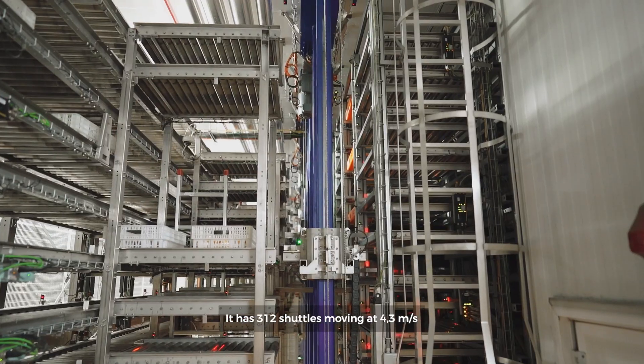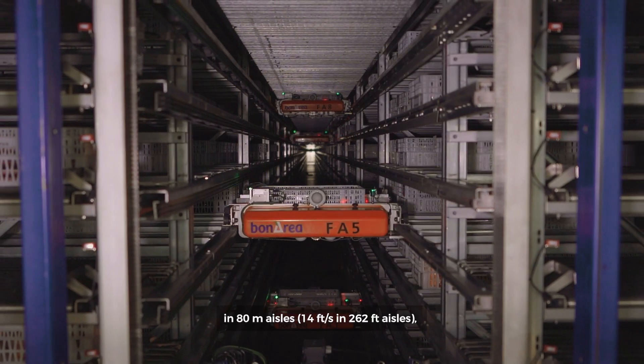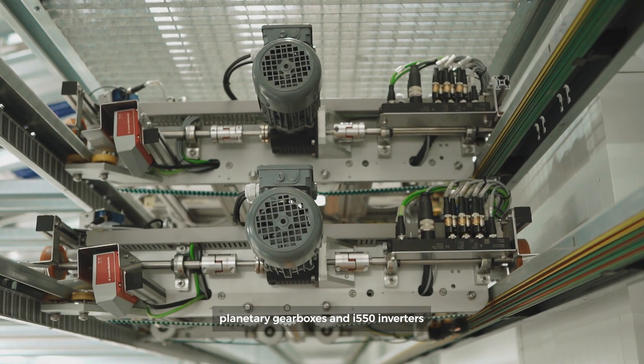It has 312 shuttles moving at 4.3 m per second in 80-meter aisles, driven by Lenze's high-frequency MF motors, planetary gearboxes, and I-550 inverters.